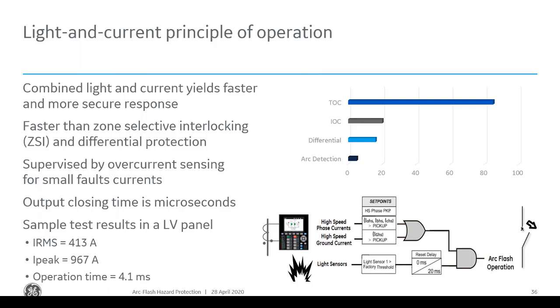Combined light and current yields a faster and more secure response. Meaning that we don't want to just look at the light, because there could be other incidents that could cause light, like somebody working on a dark switchgear and a flash, or a lightning flash. We don't want to just go off light because it's not the most secure, because we could have other sources of light. So what we do is we go with light and current, but this is a different current detection than your normal overcurrent. These are very fast overcurrent elements. We talk about fast as less than 3 millisecond pickup. So that combined with the light sensor, we get both.